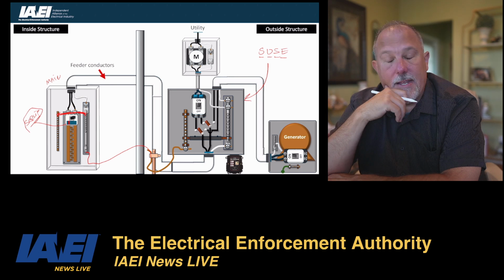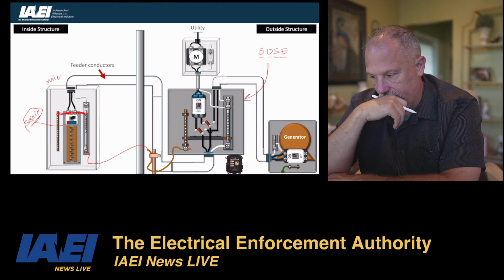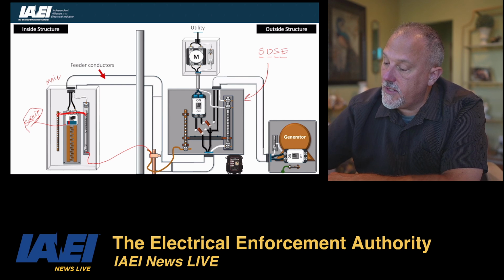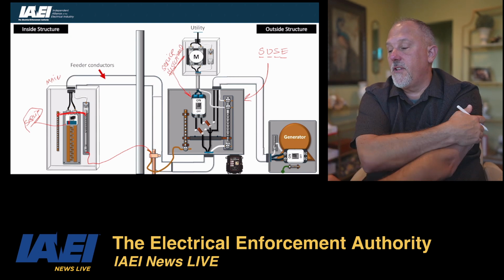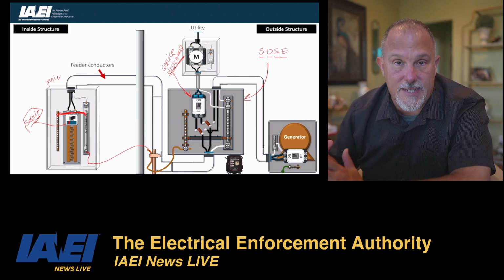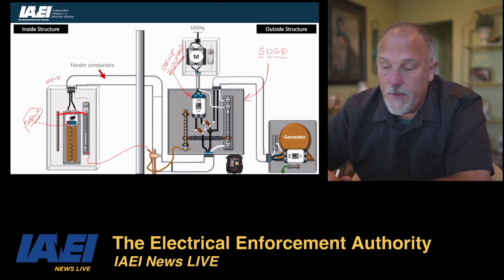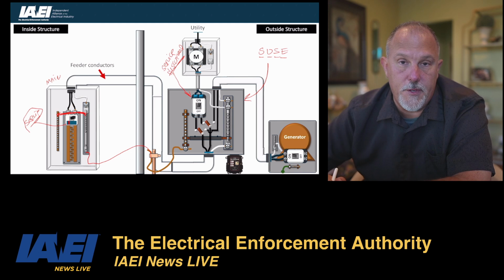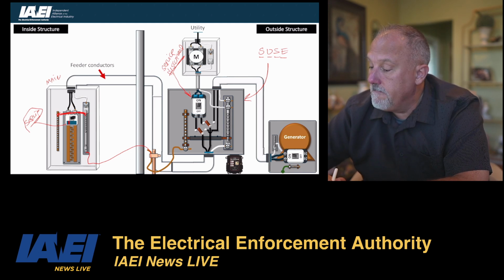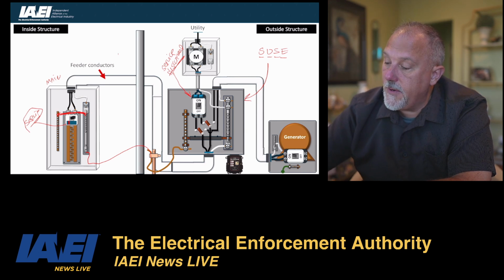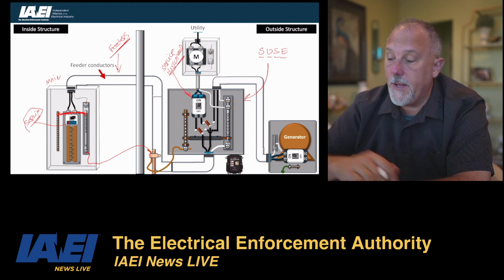No matter which way I look at it, it's complicated, isn't it? Because this will always be your service disconnecting means. That's always going to be your service disconnect, because that's the only disconnect that disconnects you from the utility. The conductors that are in this raceway are feeders. Period.